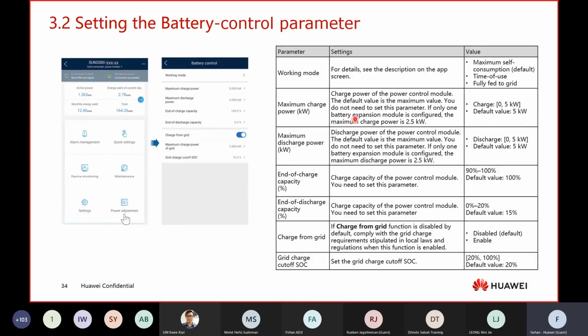So the maximum, lah. Let's say you have only one battery. This one they're talking about having 3 batteries. Then if you have one, the system will go to the default, lah. The maximum charge will be only 2.5 kilowatt. And for the maximum discharge, we also put the maximum 5 kilowatt, same as charging. The same concept they are using. If you are using one battery module, only 2.5 kilowatt can be discharged at that time. And end of charge capacity by default is 100%. But you can set it, if you want to have a longer Luna 2000 life, you can put a little bit lower.